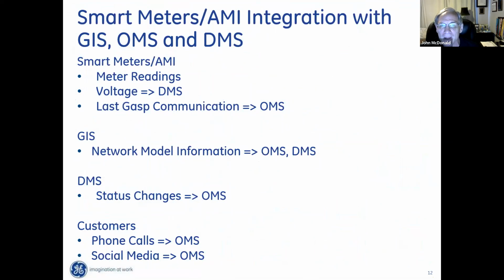So there's five key components here with the distribution part of the grid. Smart meters, the two-way metering communications, we call that AMI, automated metering infrastructure, the geographic information system, the outage management system, and the distribution management system. How well these are integrated together is really a measure of the resiliency of that utility's grid, okay? Now, smart meters, in addition to meter readings, we get the voltage from certain smart meters at the ends of certain feeders. We ping those meters to get the voltage and put it in the distribution management system.